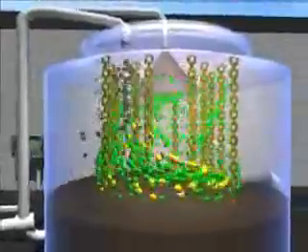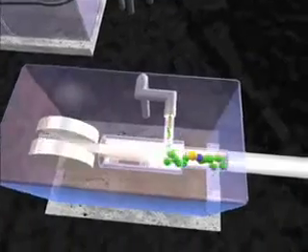The aggressive trace gas hydrogen sulfide is now extracted from the biogas in a biological desulfurization plant. By introducing air into the container, certain bacteria cultures are able to establish colonies on the chain. Here they decompose hydrogen sulfide into harmless sulfur and water.